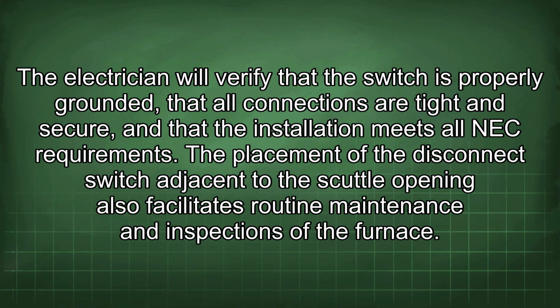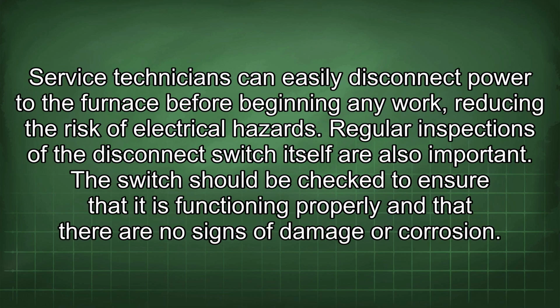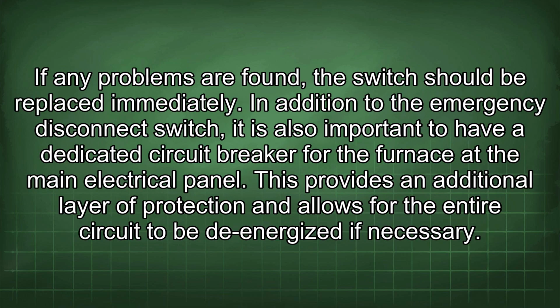The placement of the disconnect switch adjacent to the scuttle opening also facilitates routine maintenance and inspections of the furnace. Service technicians can easily disconnect power to the furnace before beginning any work, reducing the risk of electrical hazards. Regular inspections of the disconnect switch itself are also important. The switch should be checked to ensure that it is functioning properly and that there are no signs of damage or corrosion. If any problems are found, the switch should be replaced immediately.